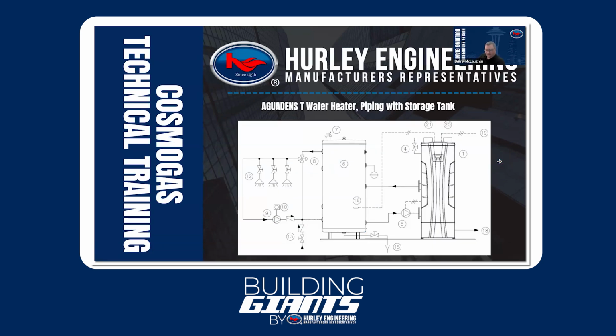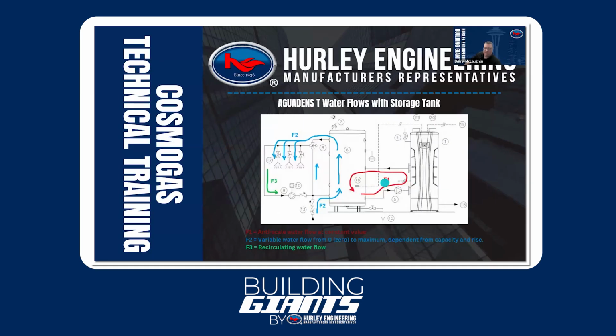And so our third idea here, or system here, is a storage tank. So this can be done as well. And it looks more intimidating than it is, but we've still got the same three flow circuits. Between the tank, we're keeping that one circuit so we keep flow in the boiler. Our circuit number 2 is our domestic water load going to the facility. And our circuit 3 is our recirculation coming back to the anti-scald or three-way mixing valve.